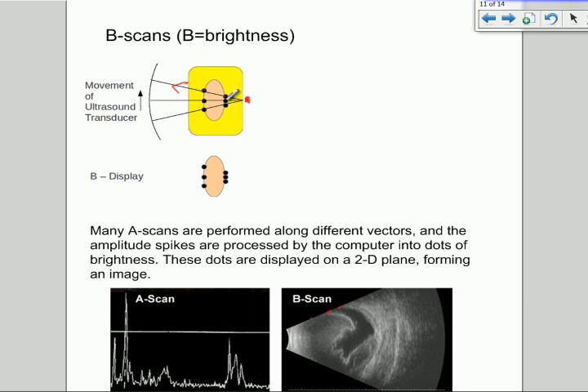And then we send an ultrasound pulse out at a slightly different angle into the body. So we're going to get a dot there and a dot there, as the pulse comes back here, and then the pulse comes back from here. So that would be a dot there and a dot there. And we do it at many different angles. So on this little diagram up here, that's the third direction. So we'll get a dot there and a dot there. Or on this one, it would be a dot there and a dot there. And we keep going. And we get lots and lots and lots of dots.